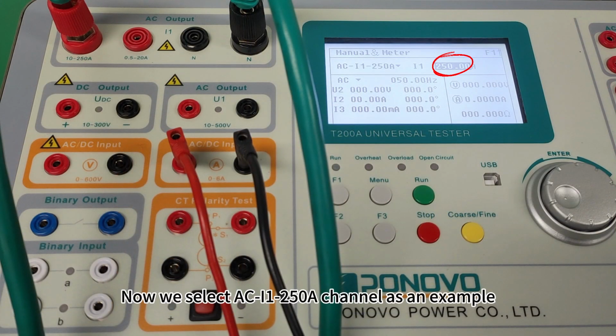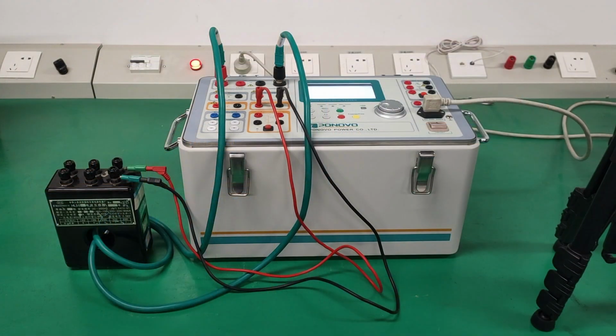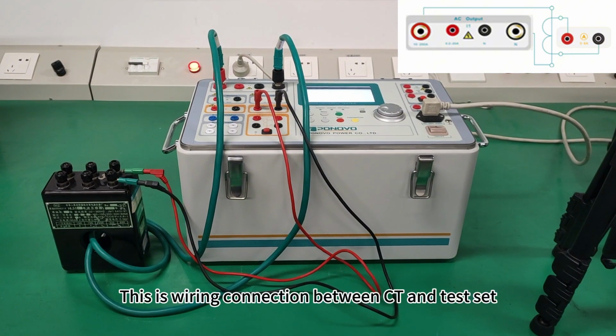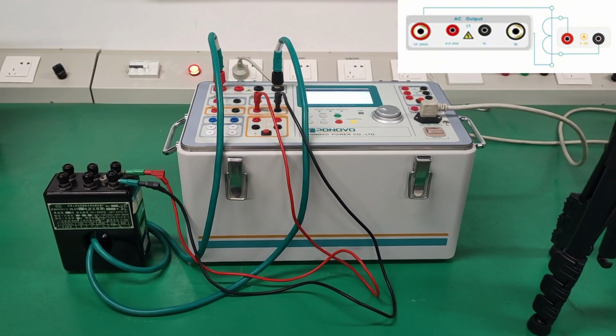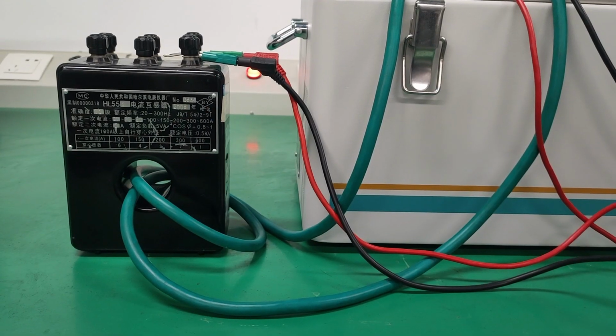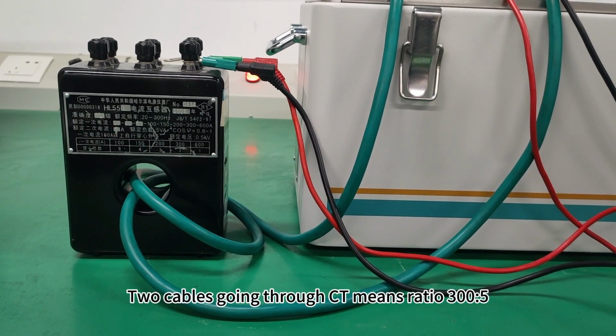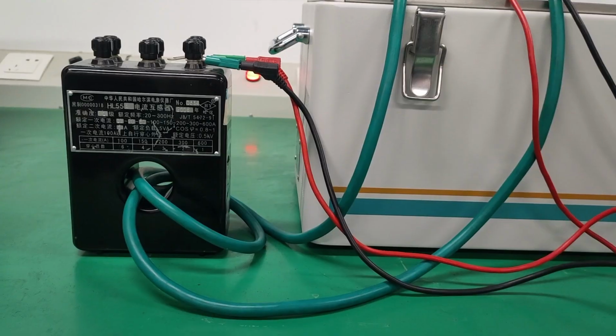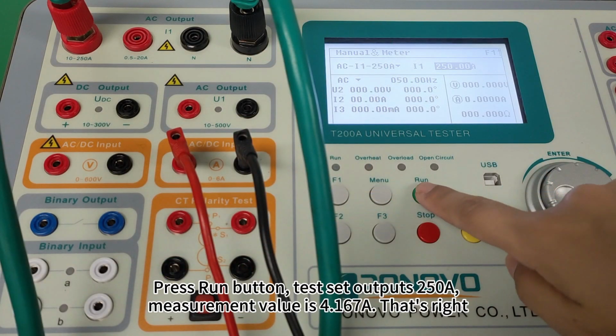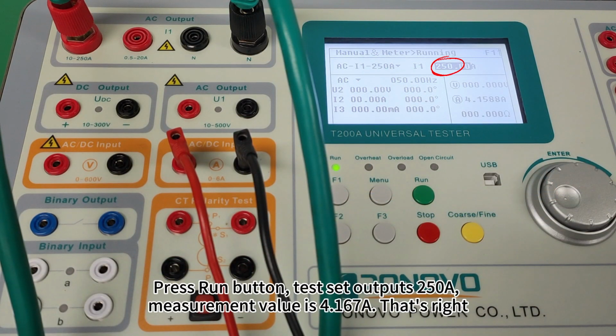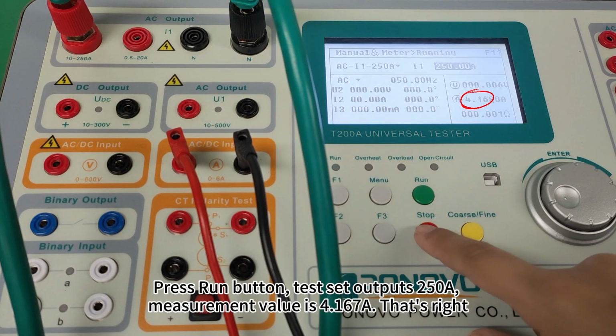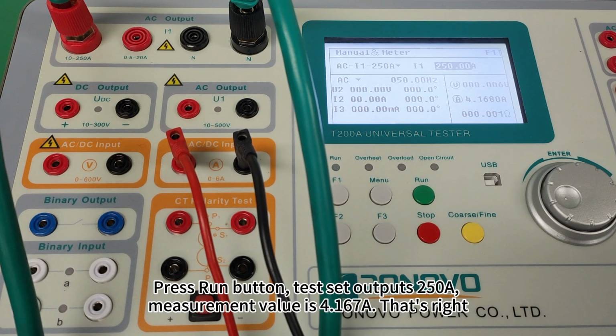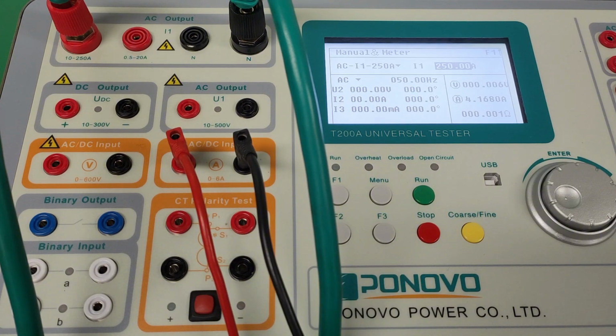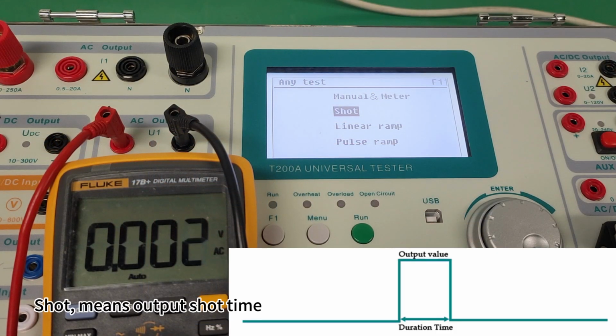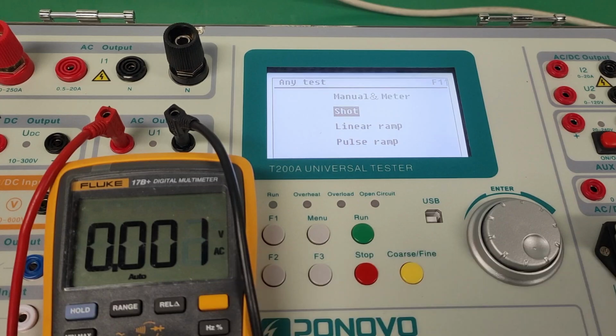Now we select ACI1 250 amperes channel as an example. This is wiring connection between CT and test set. 2 cables going through CT means ratio 300 to 5. Press run button, test set outputs 250 amperes, measurement value is 4.167 amperes. That's right. Shot, means output shot time.